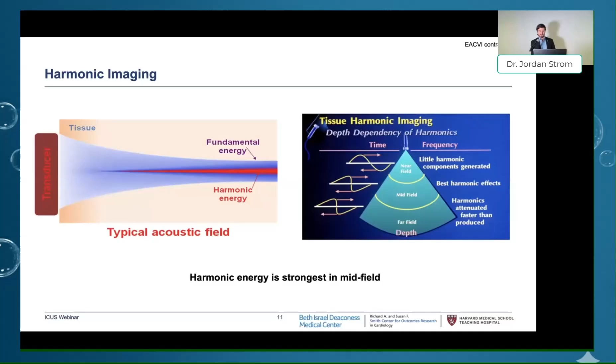And what we see is a couple of peaks. We see a subharmonic that's below the fundamental frequency, but we also see a second harmonic, a third harmonic, etc. And one of the nice parts about these bubbles is not only do they have a nice property and ring at these second harmonic frequencies, but they also have nonlinear effects. They compress or they expand more than they compress, and that causes a nonlinear signal, which ultimately we can pick up on selectively to be able to bring out the image.